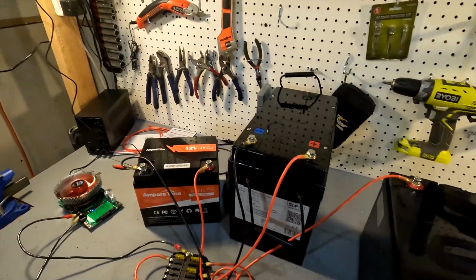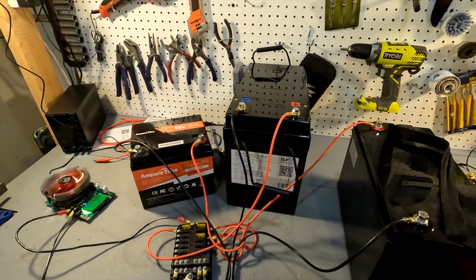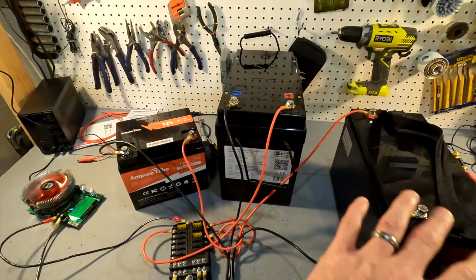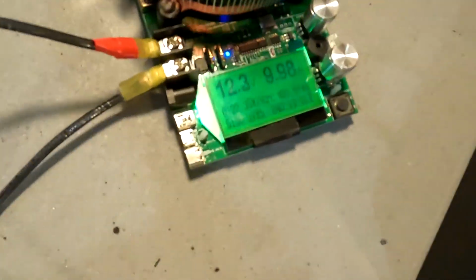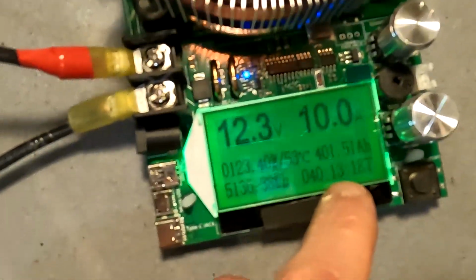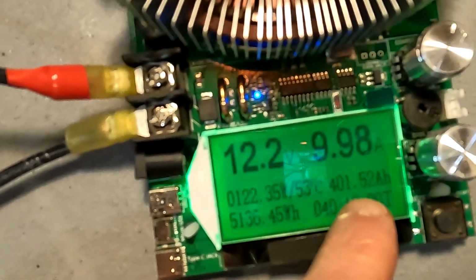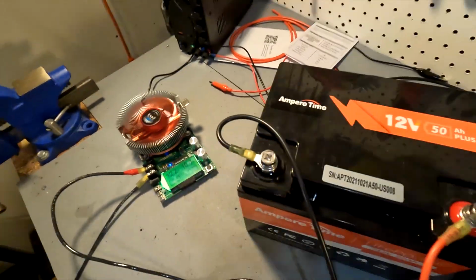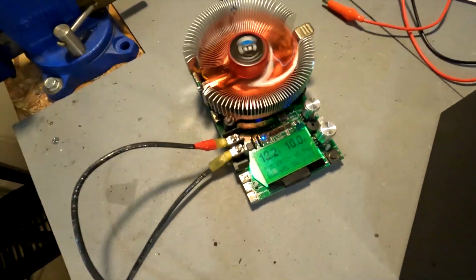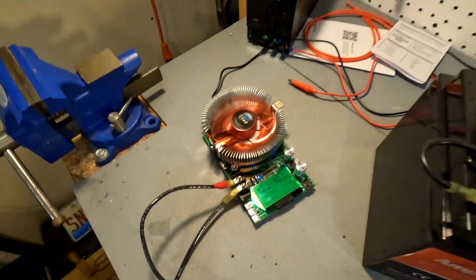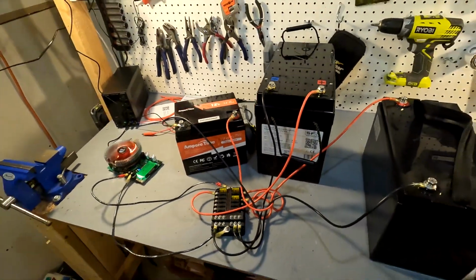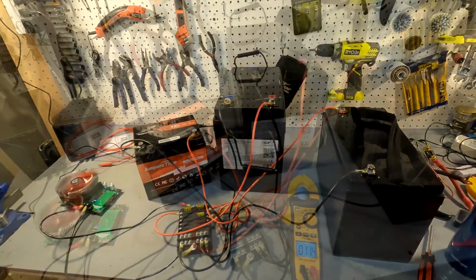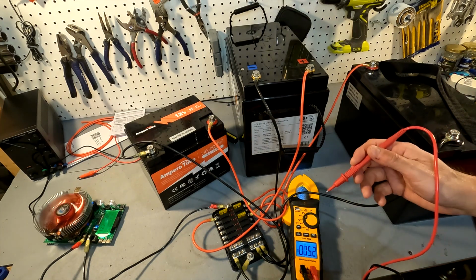So out of this 425 amp hour bank in total, we've used up 400 amps of it, right there. Our voltage is at 12.2, but let's go ahead and check the voltages of all the batteries to see where they're at. The tester says 12.2.